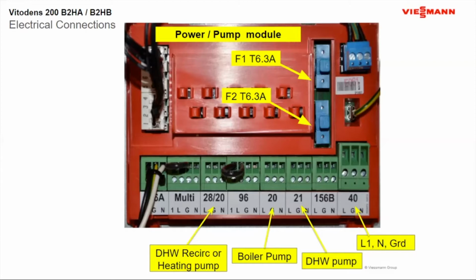domestic recirculation. Your multi-plug, that's where they recommend you would put the low water cutoff. You can put it there, or you can put it at your 40 plug, which is always going to be your incoming power here. So you could wire it to your low water cutoff and then come into the boiler and power your boiler through your low water cutoff. If you do use the multi-plug, you do remove the jumper up, and then it's power up and power back down to the multi-plug.